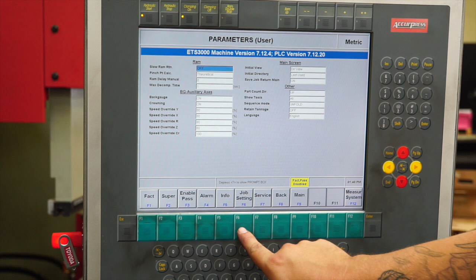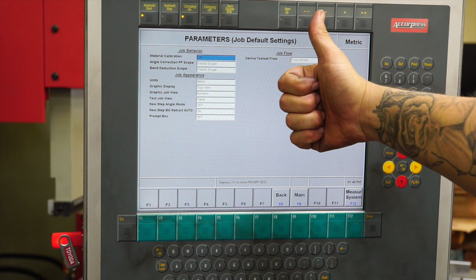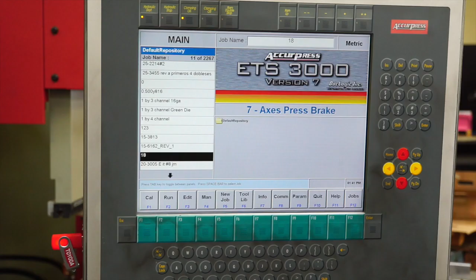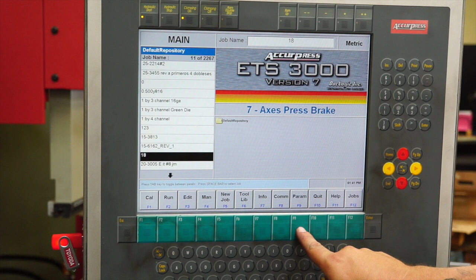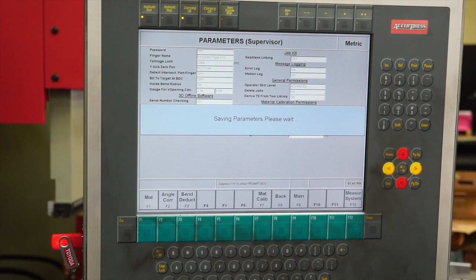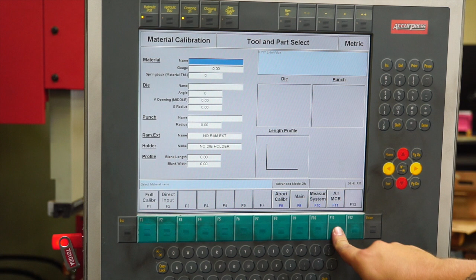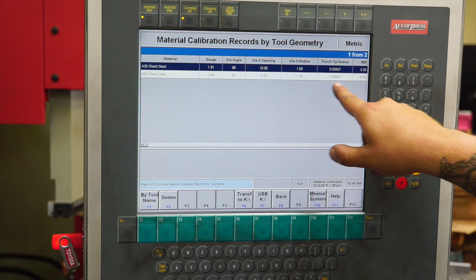Okay, to turn on material calibration, we hit parameter, then we're going to go over to job setting, and then that first entry there, we just hit that, make sure it's on and not off. To see the data that's been saved, press parameters, super, hit material cal, and then the last button, F11, all MCR. This will display all the data that's been saved from your calibration and every material as you do it.